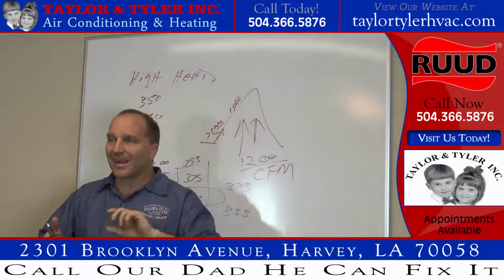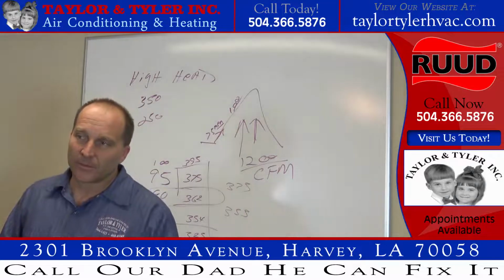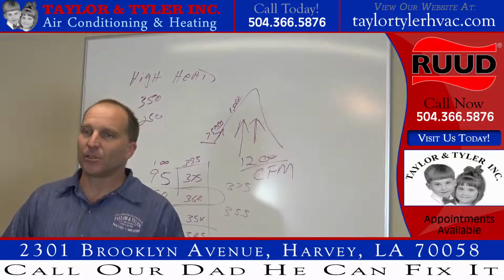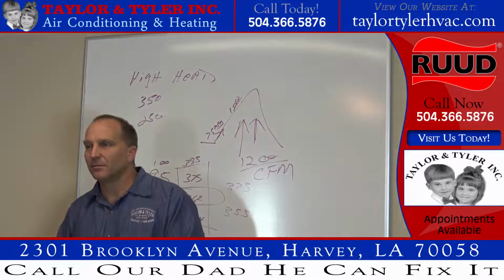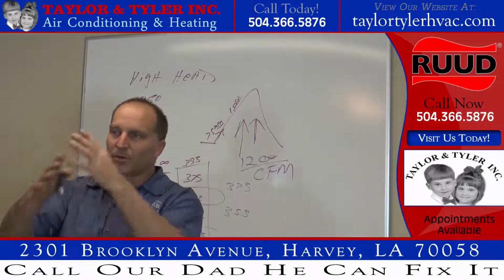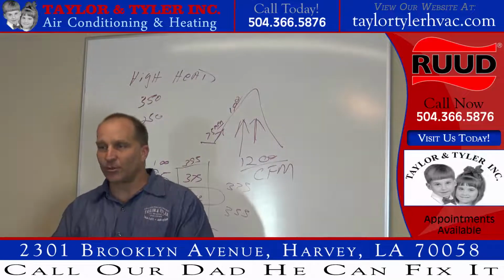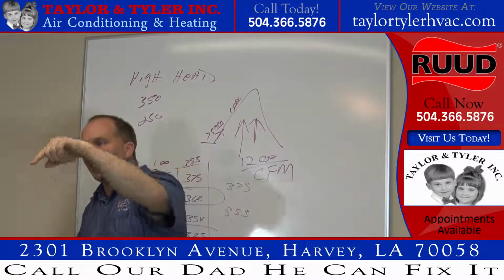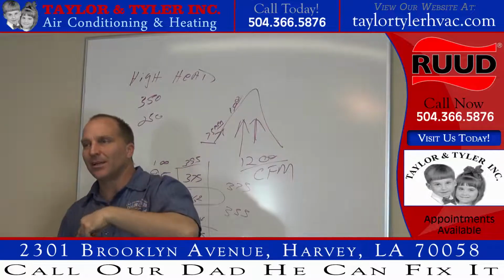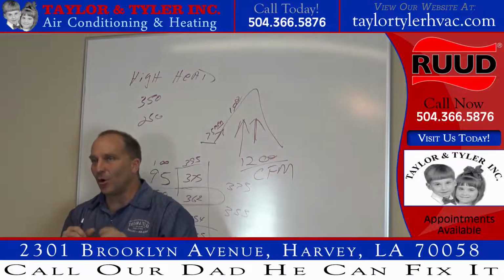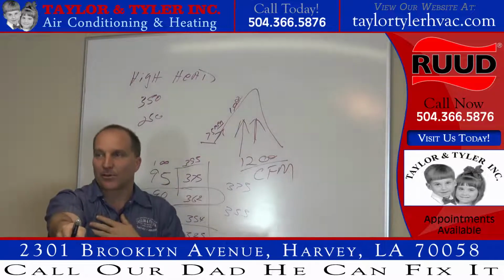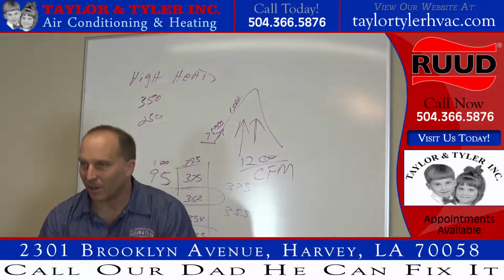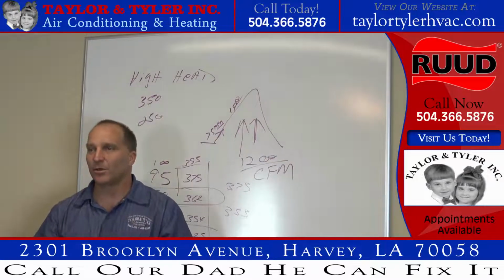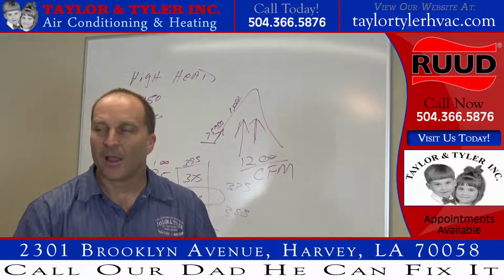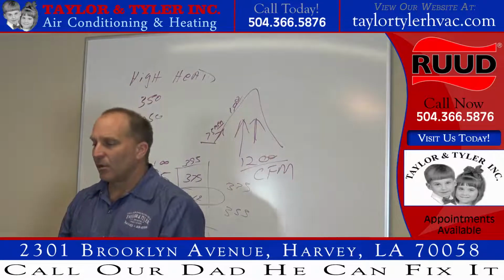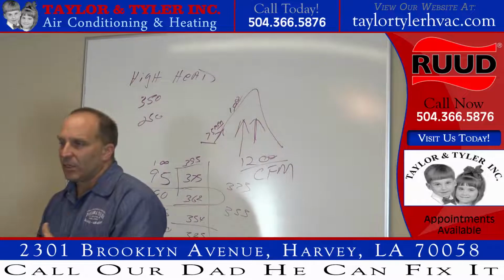Now, will you open high side and low side in order to recover it through? No, what you do is you open high side first. Why? Because it's liquid. So you're going to suck in most of the liquid first. So that natural pressure pushing through the recovery machine into the tank, and the tank is in a negative pressure, it's going to be sucking in. Well, if you only open the liquid side, you're going to suck in mostly liquid first, right? Mm-hmm. Now when you go turn the recovery machine on, you're mostly sucking out gas, and it reduces your recovery time. Make sense? Yeah.